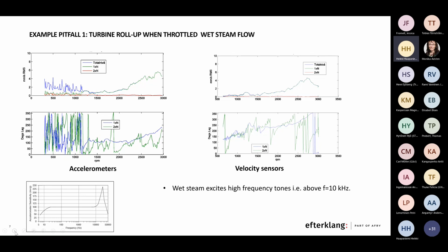Pitfall number 1 concerns turbine run-up when you throttle wet steam flow. You started with accelerometers, ICP sensors, measuring during the throttling range, roughly between 300 and 1100 RPM. As you see, in the upper window is the amplitude in millimeters per second, and in the lower graph you have the phase. In this RPM range, you have a random phase. You also see that the total level is much above the natural unbalanced forces from the first order, which is below here. But after the throttling finished, it works perfectly well.